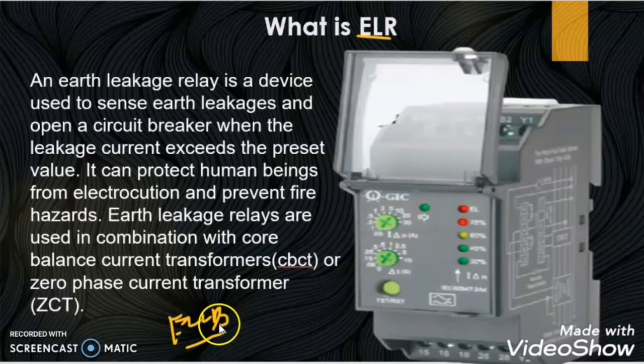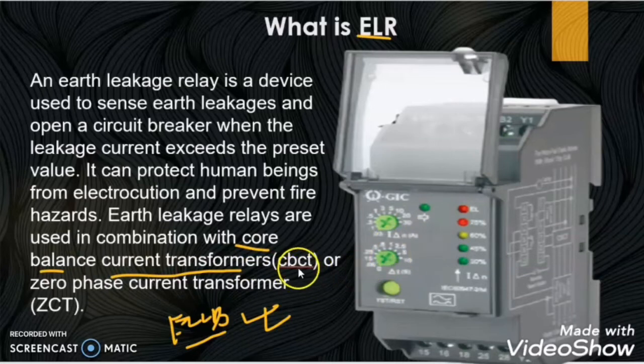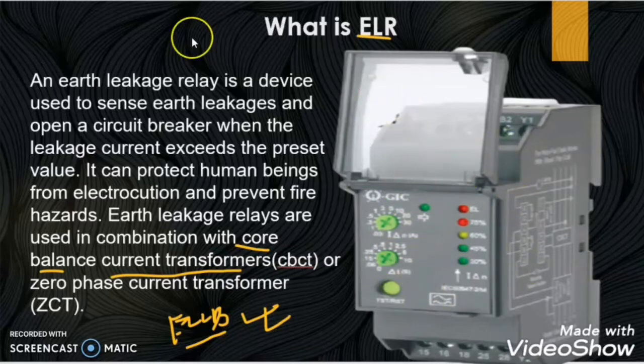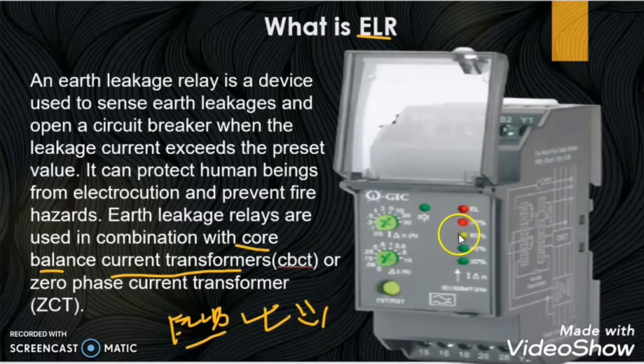Earth leakage circuit breaker senses the earth leakage current and breaks the circuit by its own. But earth leakage relay senses the earth leakage current by the help of core balance current transformer, and whenever the earth leakage relay finds this sensed current more than the preset value for more than the preset time, then it gives command to the circuit breaker or to the contactor to open in order to break the circuit. The ELCB is used for lower current ratings but the ELR can be used for higher current rating operation.